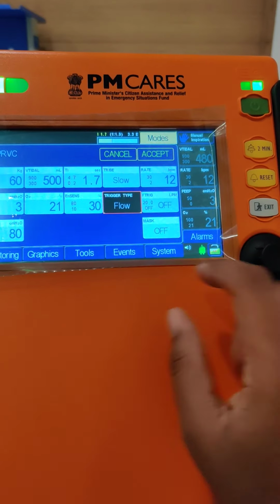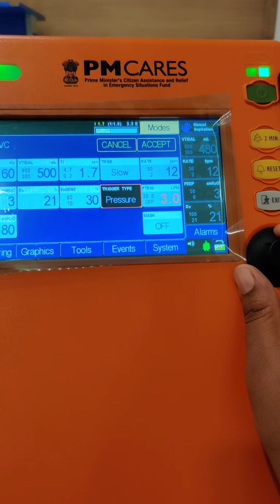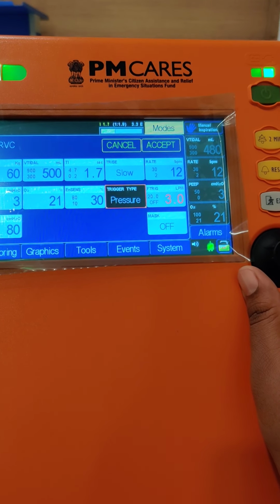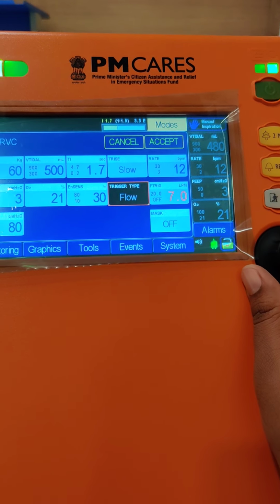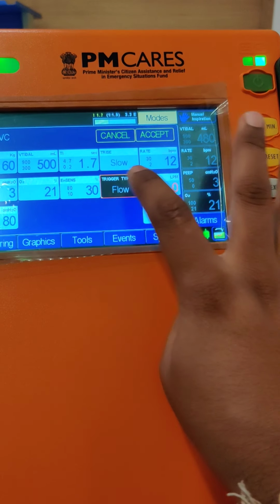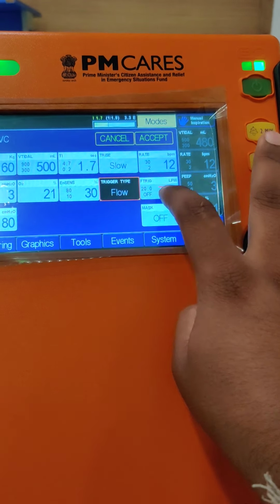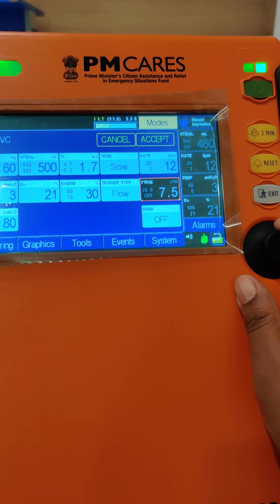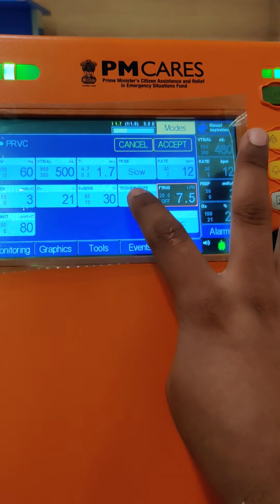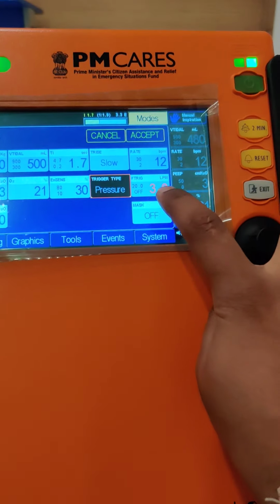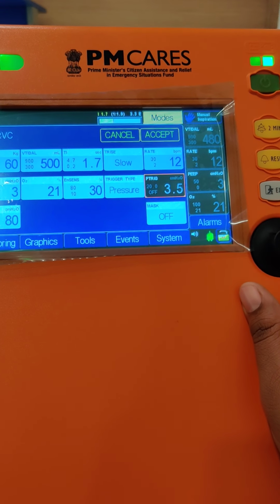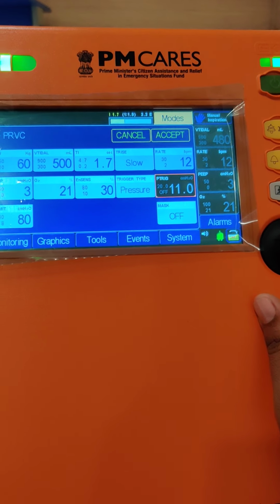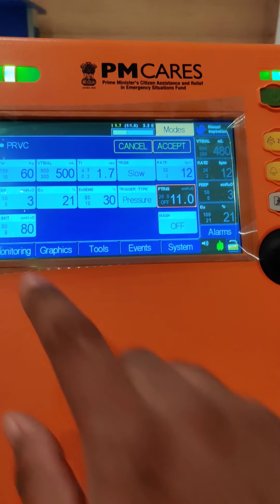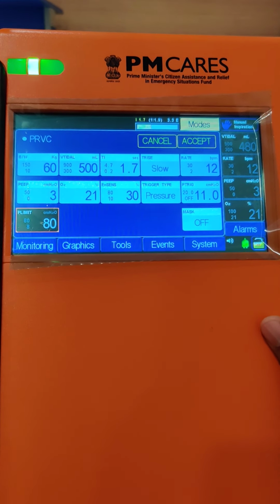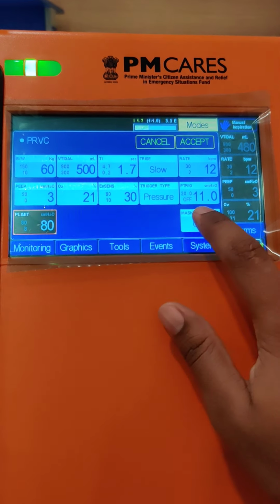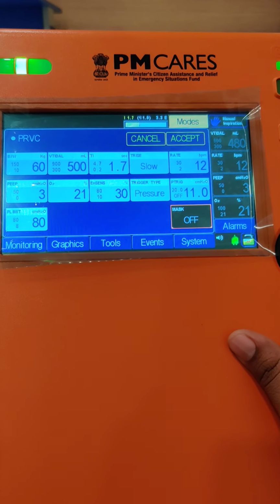Then we have given both types of triggers, the pressure trigger and the flow trigger. If you want to set the flow trigger, you can set values between 0 to 20 liters per minute, and if you set pressure, you can set the pressure between 0 to 20 centimeters of water. Then we have this pressure limit that you can set up to 80 centimeters of water, and you can use the mask on and off feature for both.